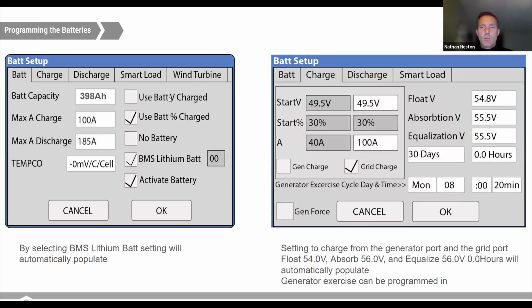Best practice with these battery systems is to actually set up without communications first, so that if communications are ever lost, then the inverter will default to those values. So the first step, and best practice, would be to go through a program with voltages without communications enabled. We would set our float at 54, our absorb at 56, and then the equalize we disable by setting that to 0 hours. The equalize is a lead acid function to burn sulfur off the plates.